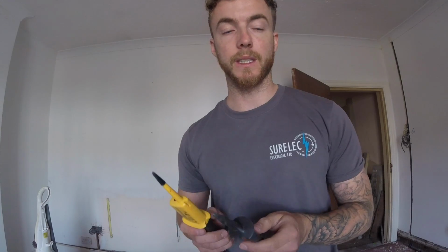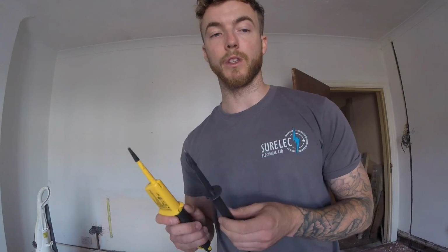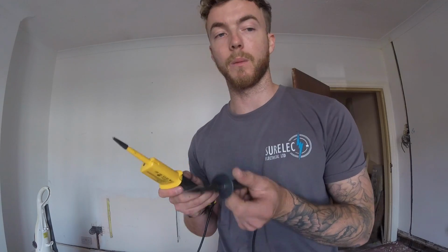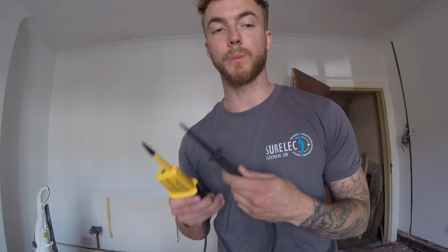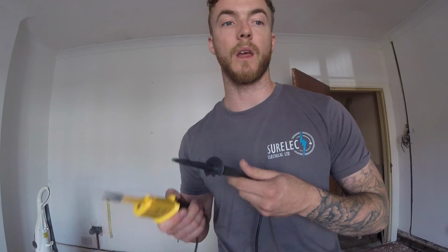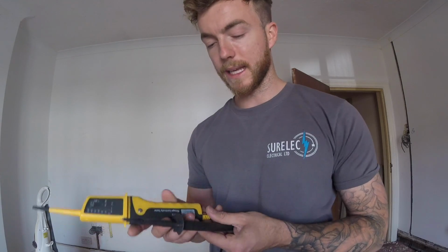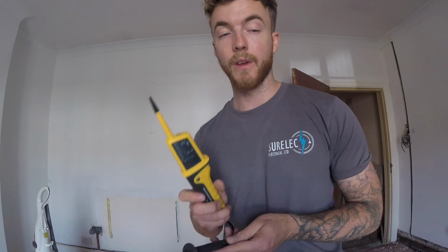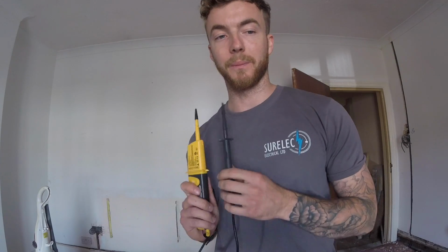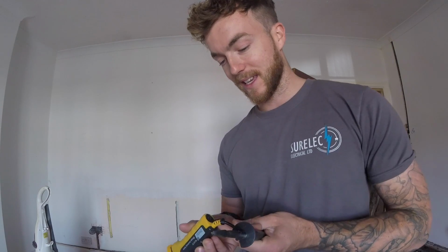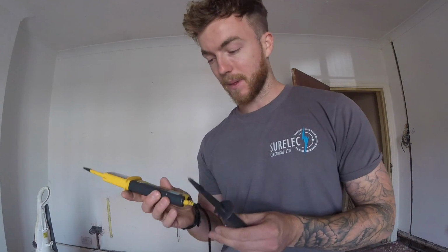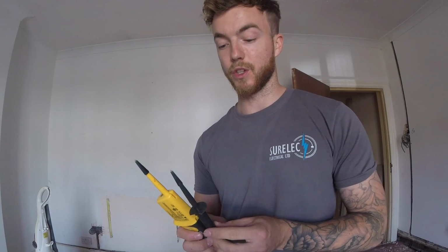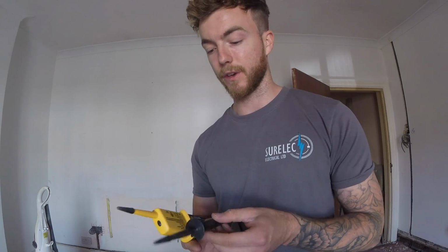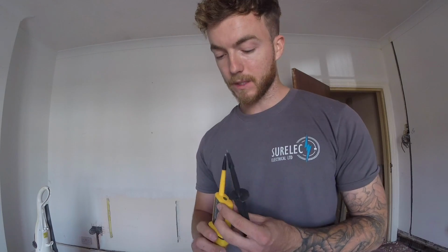Obviously, when you're doing safe isolation, a lot of people use proving units to prove these first and then prove again once you've tested. But all I normally do is prove on a known supply somewhere else, the incoming terminal of the main switch, for example. So yeah, these are something every electrician should have. A lot of electricians probably don't use them that much until their annual inspection comes around. Yeah, I won't say any more. But obviously a good thing that you should have and use quite frequently, to be honest. This one's quite nifty as well.